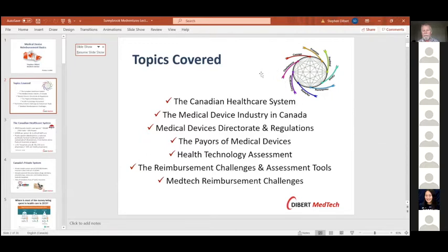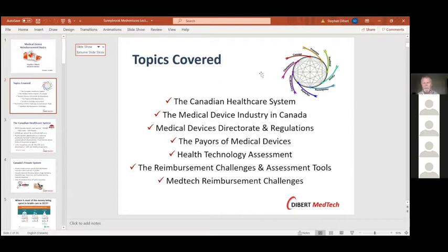Now, in the top right-hand corner here, this is the FDA's regulatory model out of the US. As you can see, it's a concept to obsolescence. So it's a life cycle model, which they've always used in the US. Canada has recently committed to using the same concept. So they'll be doing pre-approvals, the ongoing monitoring, the post-market activities, all those things.